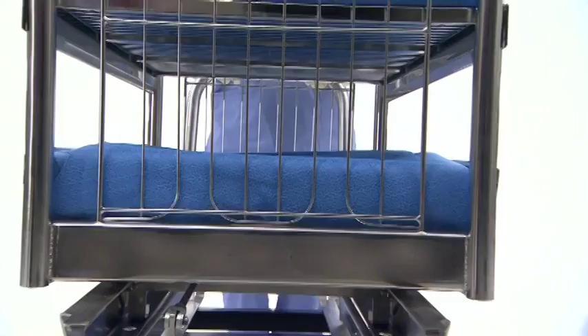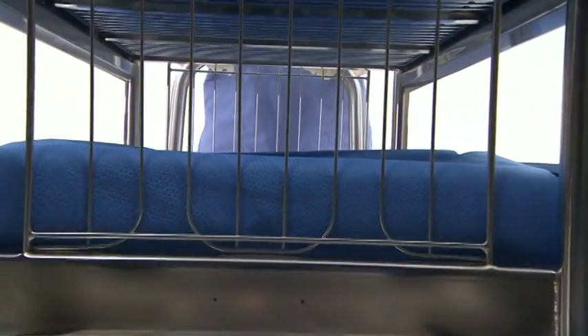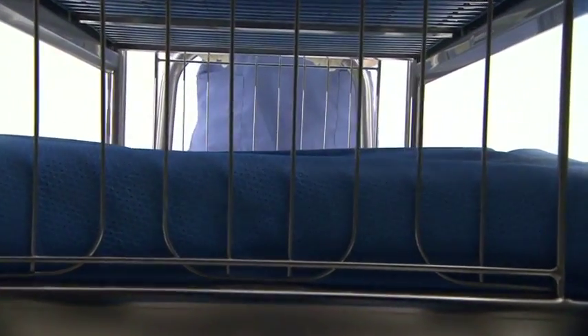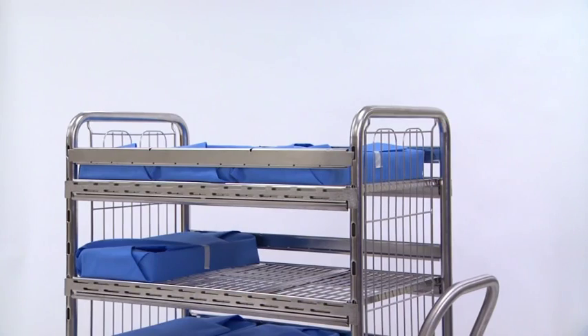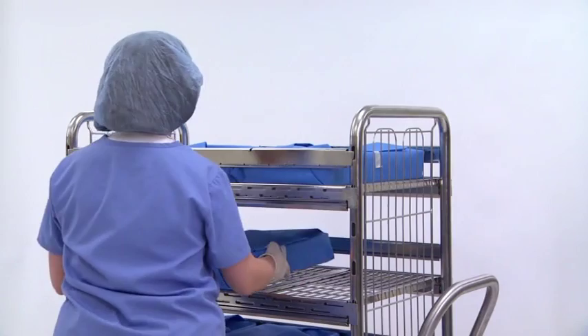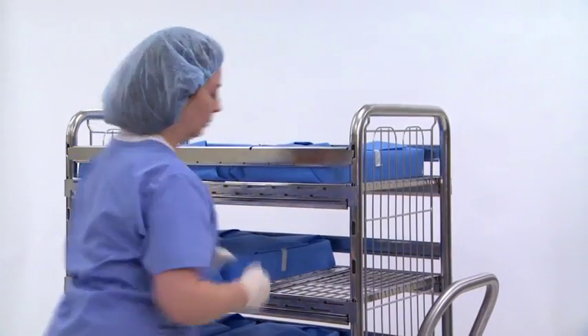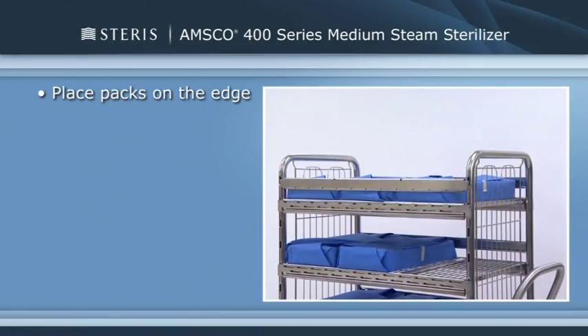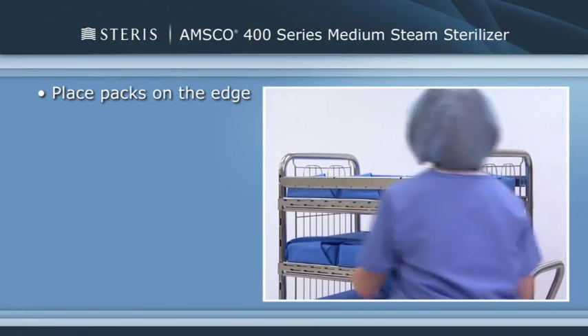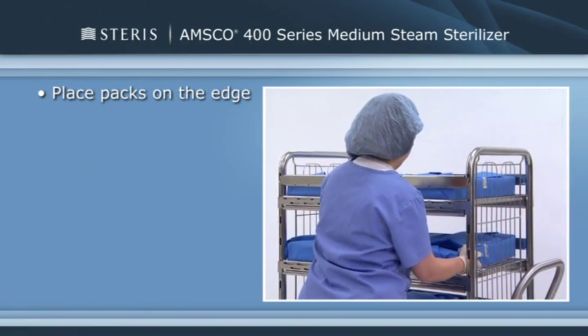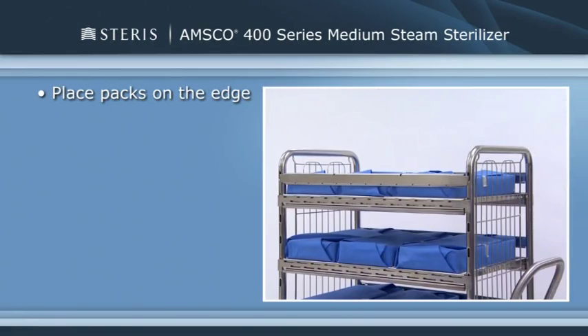Next comes placing the loads in the unit. Specific guidelines can be found in AAMI ST79. If a cycle has been run, the unit and shelves may be hot. Wear clean gloves and use clean towels as pot holders when loading. Place all packs on the edge and arrange the load to allow for maximum steam exposure so there's minimal resistance for steam passage through the load.